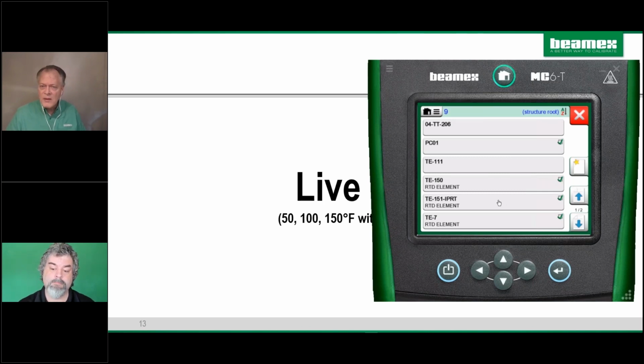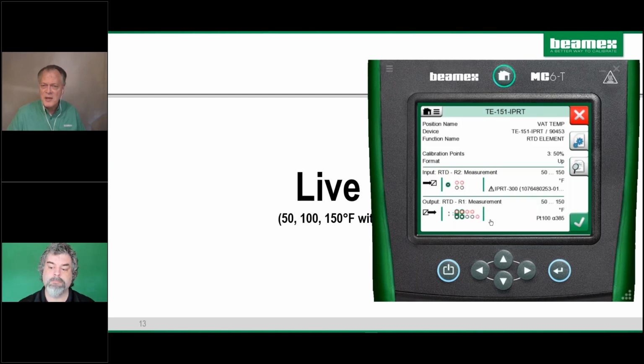So today I want to check temperature element 151, and I put IPRT since it has the reference probe in there just to remind me. But the MC6 tells you where to connect. My reference probe is hooked up to that LEMO connection you saw, and then I can have a 2, 3, or 4-wire connection here for my field probe. And there's my range, there's my identifier on the temperature probe that I'm using, so it uses the right coefficients.